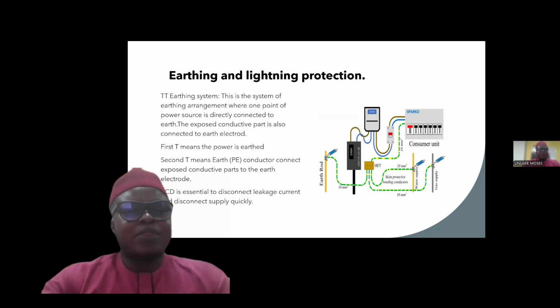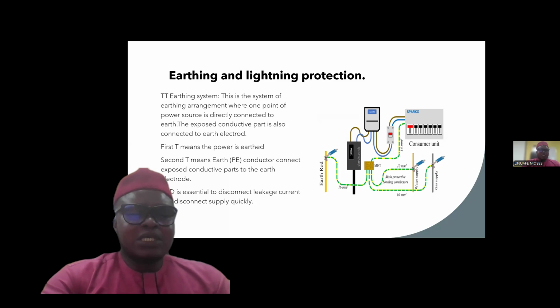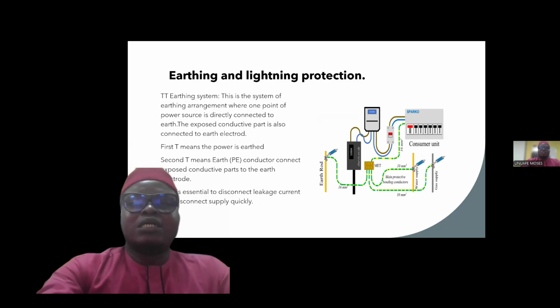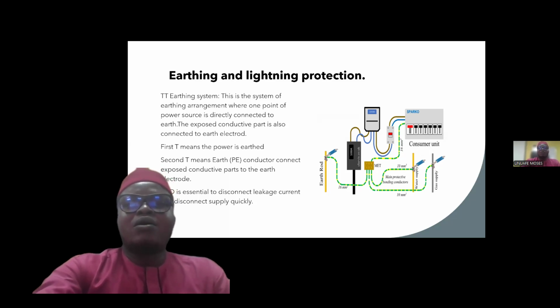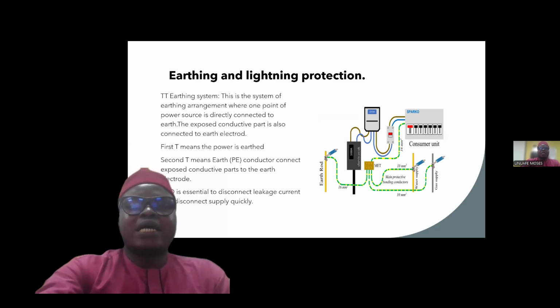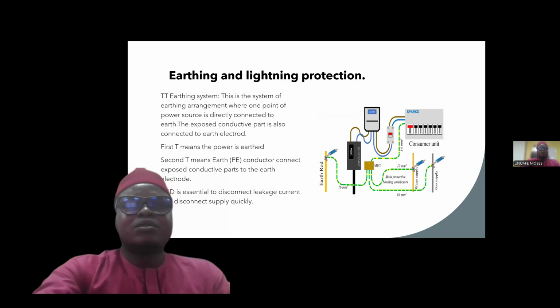On this TT earthing system, this is a system of earthing arrangement where one point of a power source is directly connected to the earth. The exposed conductive part is also connected to the earth electrode. Now, the first T in this case means the power source is earthed. The second T means that the protective earth conductor, which is PE, connects the exposed conductive part to the earth electrode. And in this, an RCD is essential to disconnect leakage current and disconnect supply quickly. Now, if you look at this TT, let's take for instance, for an example, a rural house or cottage supplied by overhead line in an area where a utility does not provide an earth connection. Just like in our areas now, you see a utility supply without an earth down to the residential.